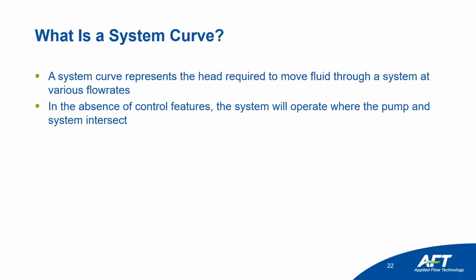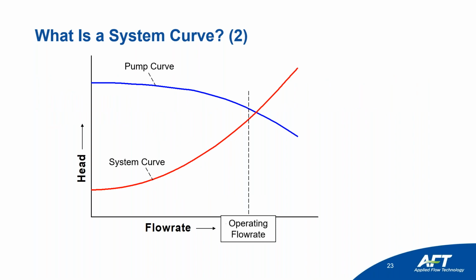What is a system curve? A system curve represents the pump head required to move your fluid through a system at various flow rates. So what it tells you is how much head you need on your pump in order to drive flow at various resistances. If you don't have any control features or control valves, your system curve and your pump curve will intersect at the operating point. So here's what this looks like.